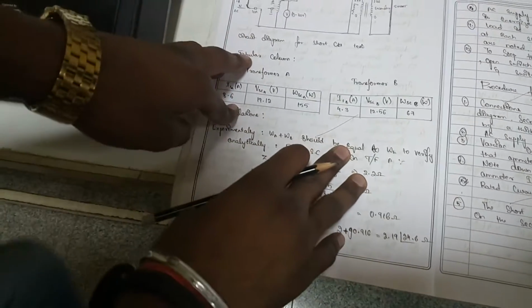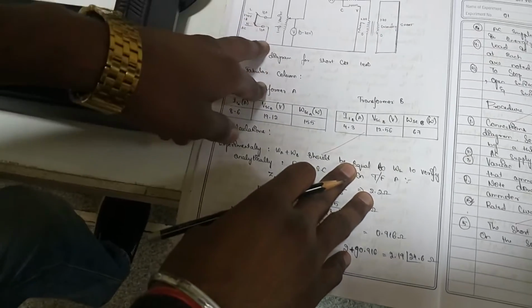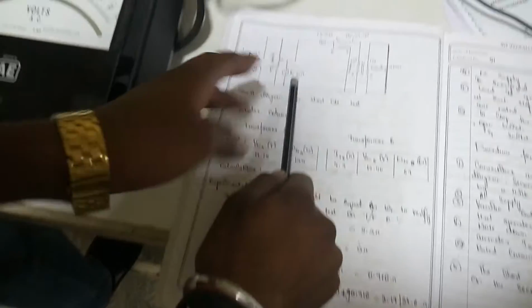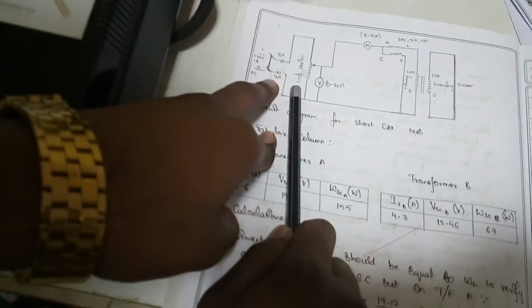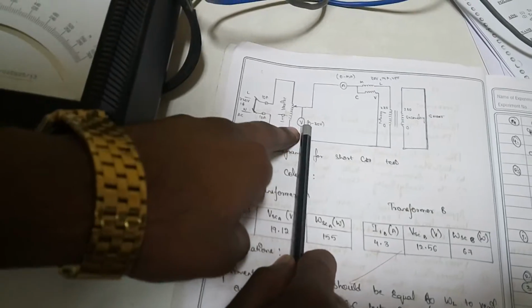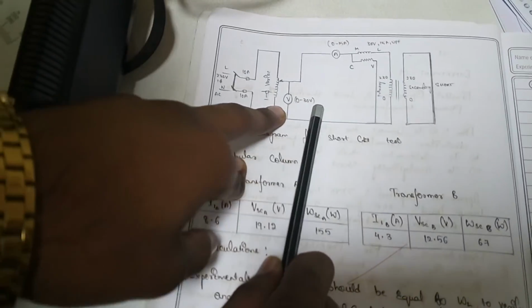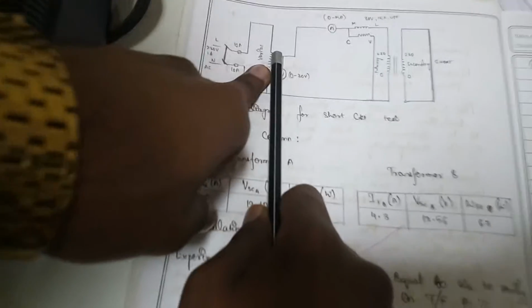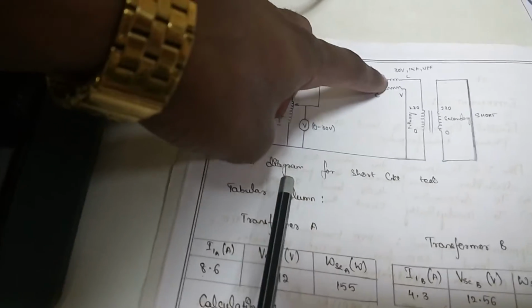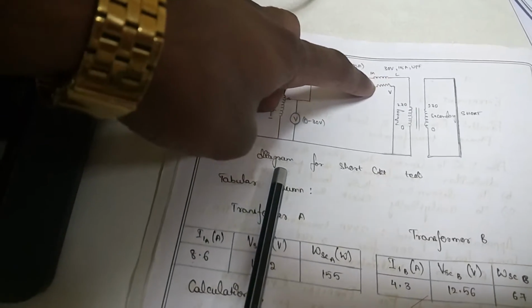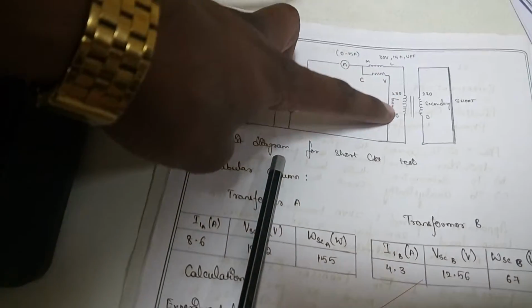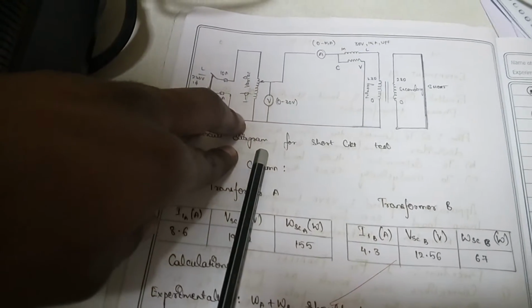After taking these values, we will be doing a short circuit test. The open circuit test, we are not going to do. I will explain it through this diagram. We will connect one single phase variac to the AC single phase supply, and across that we will be connecting one 230 voltmeter. Now from the phase of this single phase variac it will be given to the ammeter M, and then wattmeter M. M and C are shorted. L is given to this 230. And V is given to the 0 of the single phase variac.